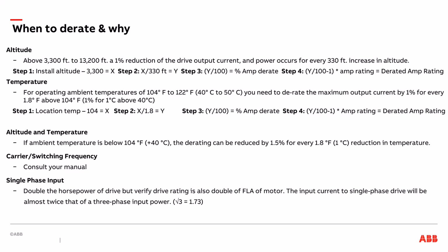The last derate condition we're going to discuss is a single-phase input for the drive. In this case, you have only 2 conductors instead of 3 supplying voltage to the input.